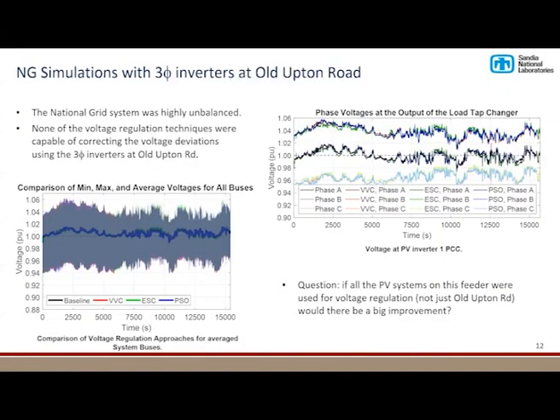Now we'll go to the National Grid simulations. This one turned out to be much more difficult. So we wanted to simulate just using the three-phase inverters at Old Upton Road, which we had access to for running the field demonstrations. In this case, on average, the voltage of this system was very close to nominal, but there's a phase imbalance. And so phase A was pretty close to nominal, but B was high and C was low, as you can see in the right plot here.